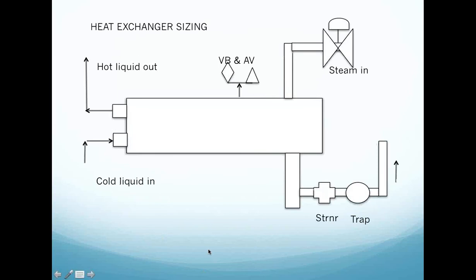of condensate. Okay. On a heat exchanger, the one thing I want to say about heat exchangers, and because I'm running a little bit behind, I'm going to move after this slide into our evaluation and trap maintenance technologies that are able to help us look at how we maintain these devices. I want to share this with you on heat exchangers, though. Heat exchangers have recently come to the front of my notepad because I've had multiple people call me recently with terrible problems with heat exchangers because of water hammer.